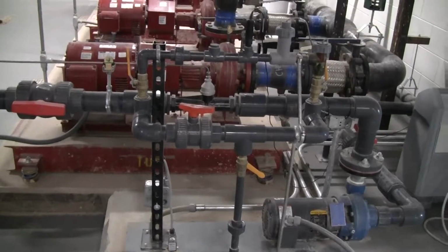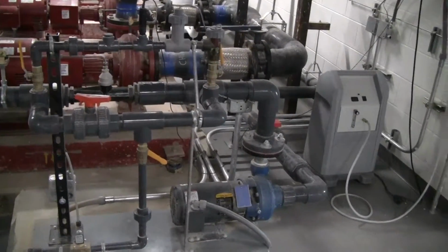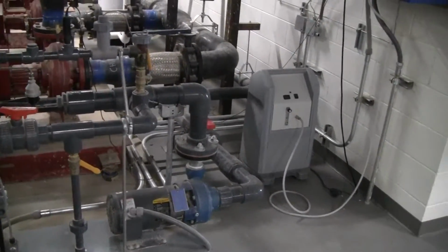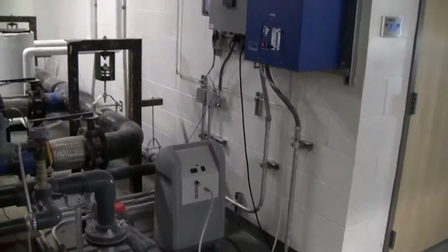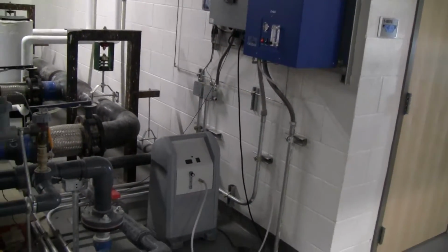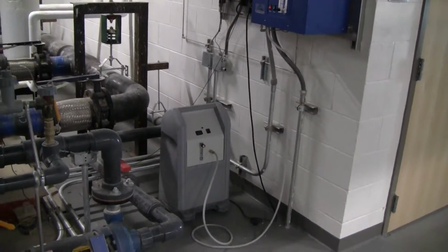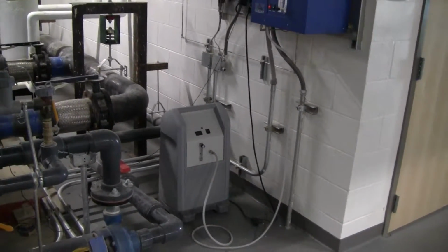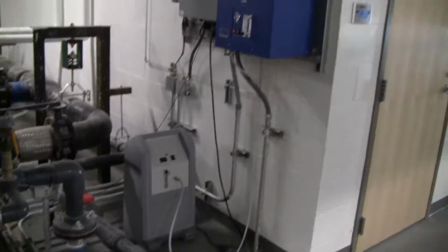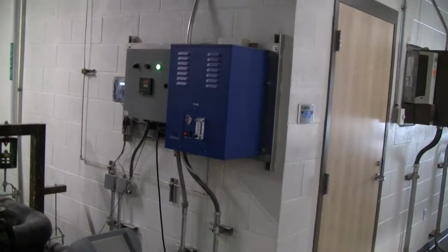With the proper velocity, if we get proper gas mixing, we get 95% mass transfer balance. The other side is the gas side. Okay? We start off with air. We strip all the nitrogen out of the air, so we have 90 to 95% oxygen going into the ozone generator, which is the blue.